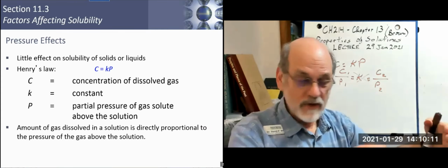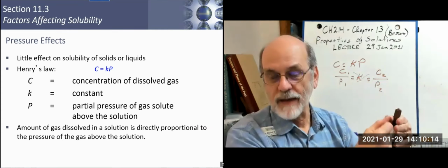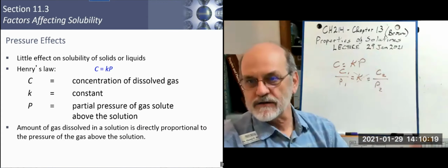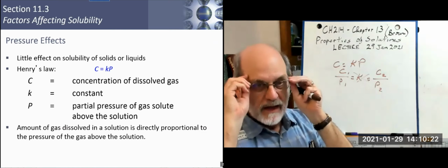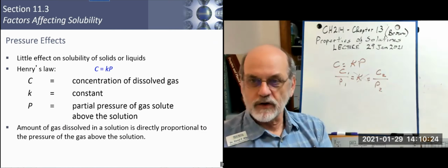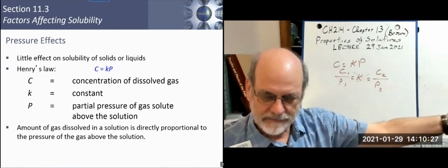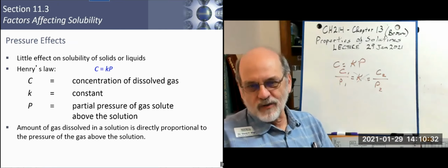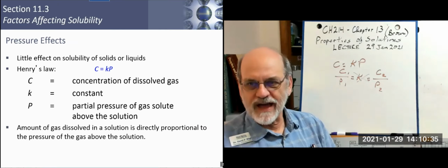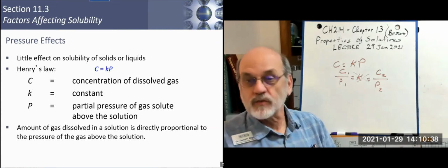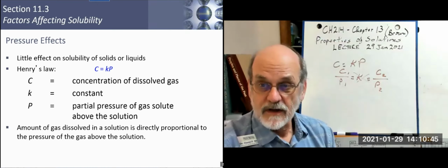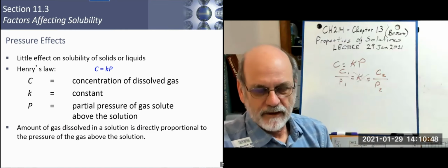On the other end of the column, the pressure is immediately 1 atmosphere. It goes from 100 to 1, and all those gases in solution just bubble out. That would be devastating for your detector, because the detector's on that end. You want to preserve your equipment, so you want to get rid of any dissolved gases that you can from your liquid. Now, that's one way of doing it. There are alternate ways, and we don't have time to talk about those now, but that just illustrates that the solubility of gases is variable in solution.